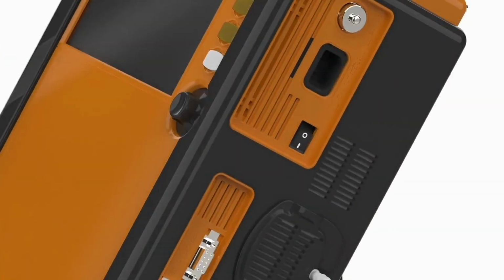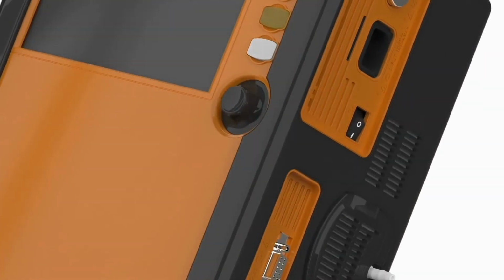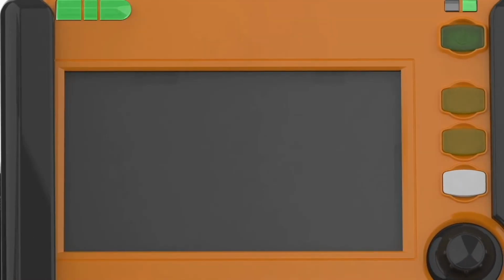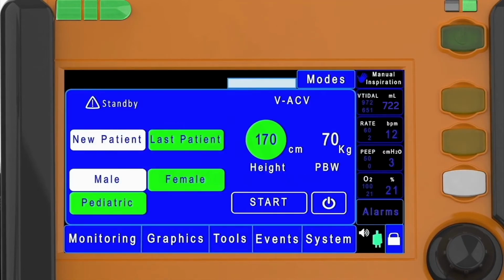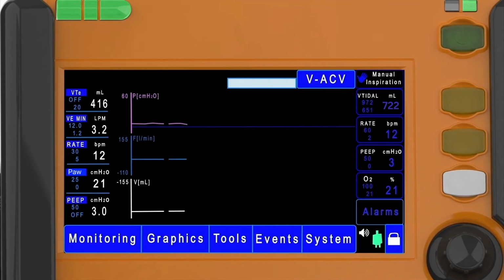To start the ventilator, you need to switch on the main switch situated on the right side of the ventilator. You will hear a beep sound. You need to press and hold the power button until the beep sound switches off. You can quick start the ventilator by either varying the height of the patient or the weight of the patient. In order to do so, select any parameter and rotate the knob to vary the value. Alternatively, you can also select the previous patient's parameters to quick start the ventilator. Once the values are set, click on the start button to quick start the ventilator.